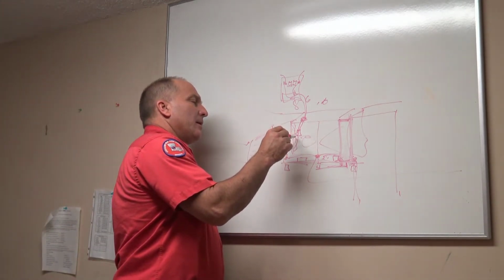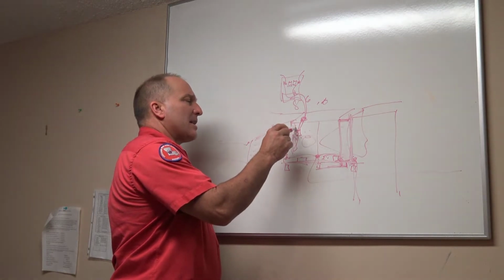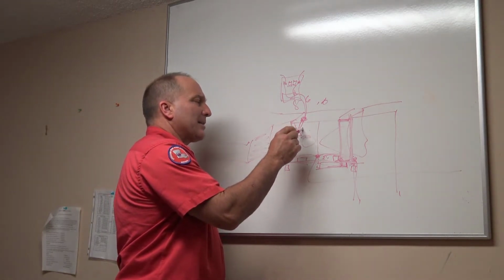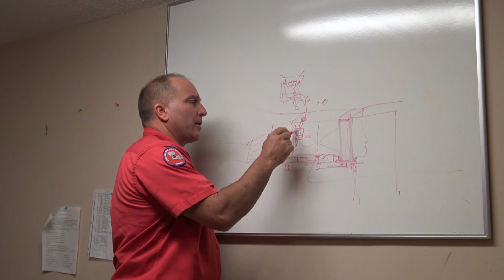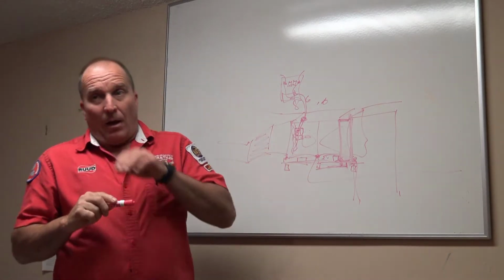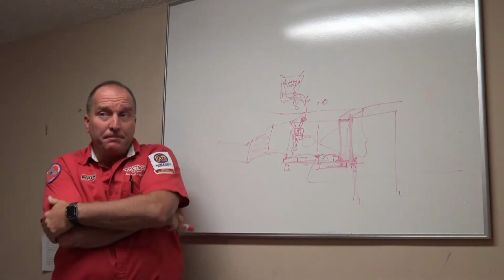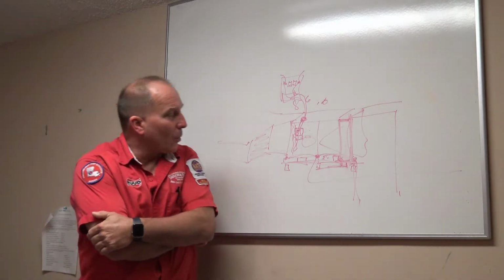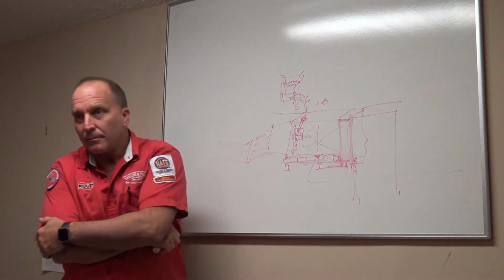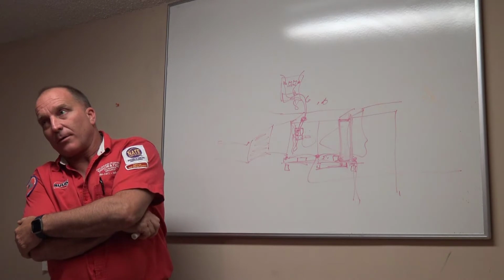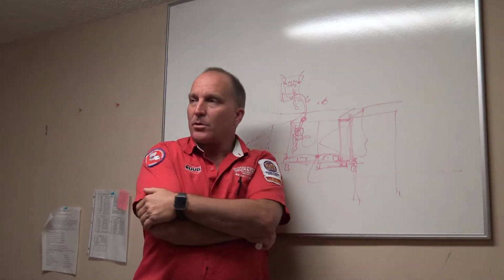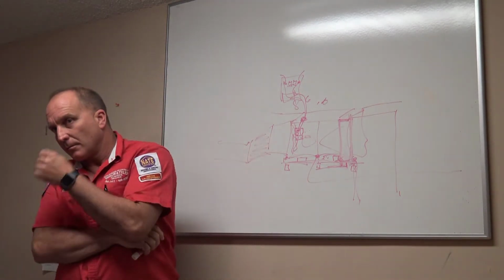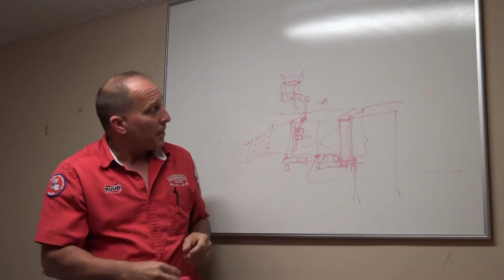If this cabinet door does not have a plastic cover over this breaker, tell me what's going to happen. It's going to get moisture. Say again? It's going to get moisture. Why? Because there's no cover. How is it going to get moisture? Where's the moisture coming from? From the coils, from the evaporator coils.